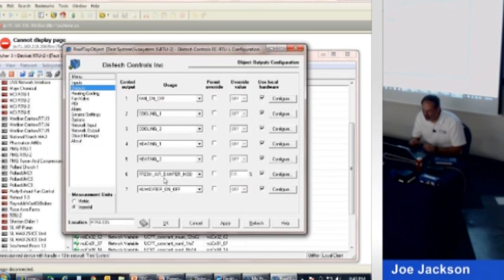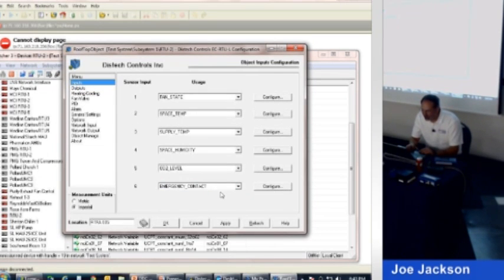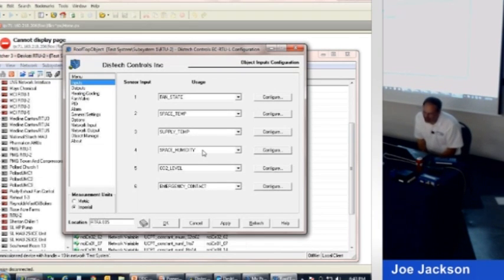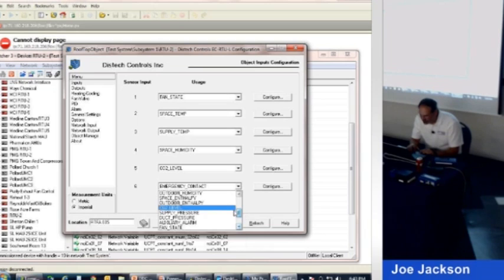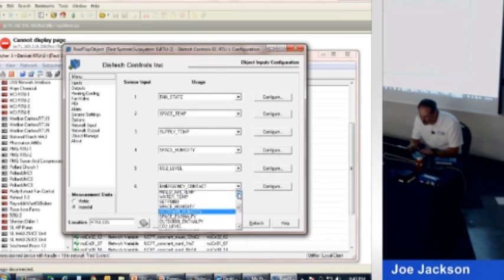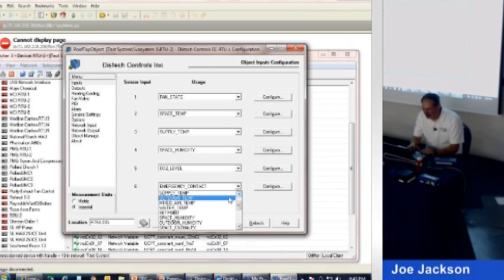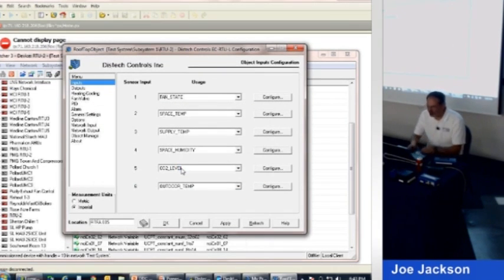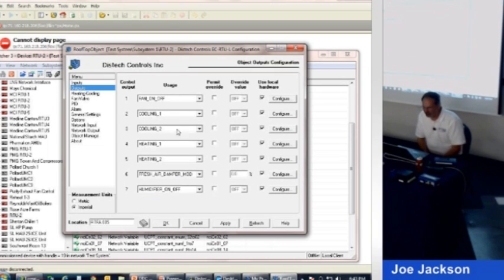Now, that's all really good. If we look back, we've got a space humidity sensor, but we're talking about controlling the economizer, and we really didn't stick an outside air temperature sensor on it. We're not really sure how to control the economizer without an outside air temperature sensor. So I'm going to find an outside air temperature sensor. Outside air temperature. And I don't know if you noticed, but you could have picked outside air humidity. This thing can calculate enthalpy. It can calculate indoor and outdoor enthalpy and look at the difference between them. But we're just going to go simple. So we've got an outside air temperature to do our economizer, and we got a humidity sensor to do our humidifier. So now all this kind of makes sense.